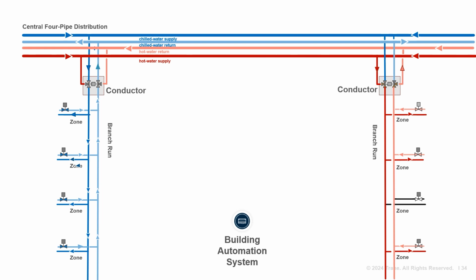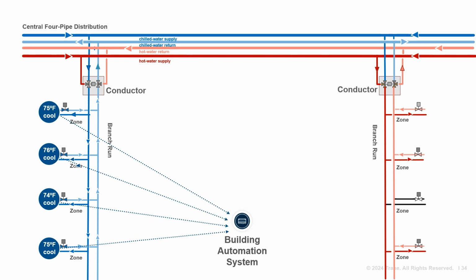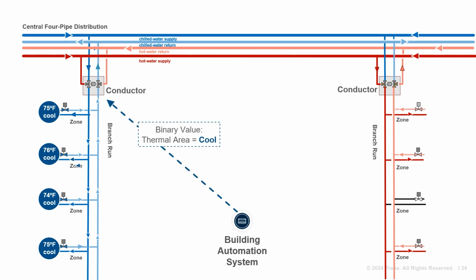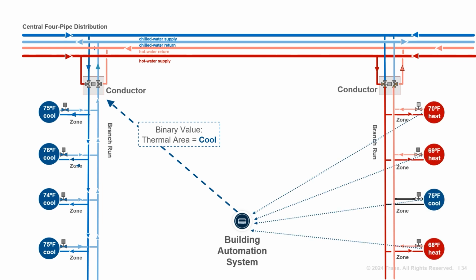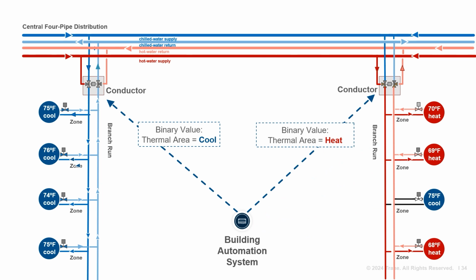During the shoulder months, the heating and cooling demands may vary depending on the zone. The south side of the school may require cooling, while the north side may require heating. The fan coils serving the south wing all call for cooling, so the DAD sends chilled water to the zones in that area. For the north side, all but one zone are calling for heating, so the DAD sends hot water to these zones. The distribution area director sends the fluid needed for the thermal area, but it does not control the area. The zone-level units still control as they do in the current 4-pipe system, with independent modes and independent valve control, as needed to satisfy the zone set points.